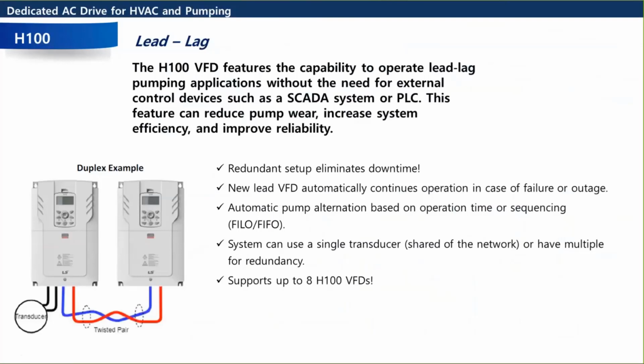So what this is, is one drive per motor, okay? And you can run up to 8 drives. So let's say you want to do 8 drives. You'd buy 8 drives, and then you'd get some wires, and you'd put them between each drive, and that would be your Modbus connection. And then you do your programming, which is pretty easy. We have a few startup guides on this.